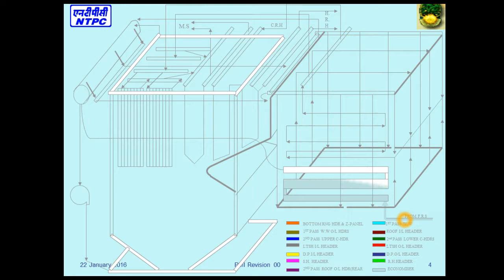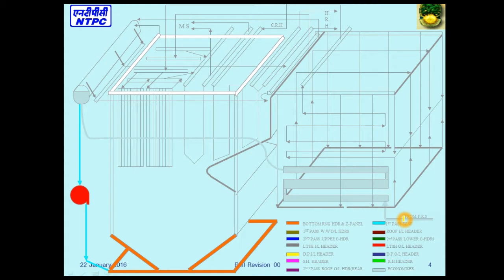From FRS to economizer tubes, economizer to boiler drums. Boiler drums to downcomers, downcomers to the boiler circulating pumps (BCP). Boiler circulating pumps back to the downcomers, then downcomers to the bottom ring header of the boiler, and then to the water walls — front and rear water walls.